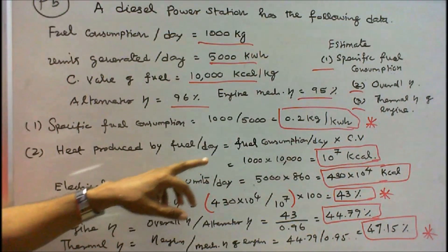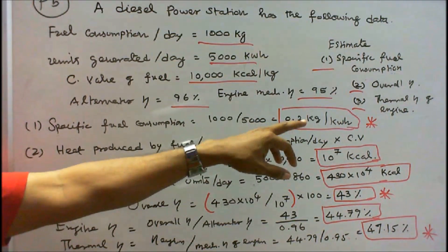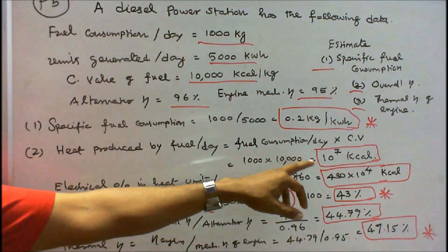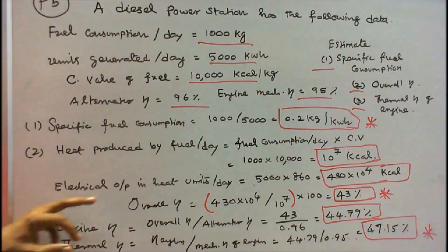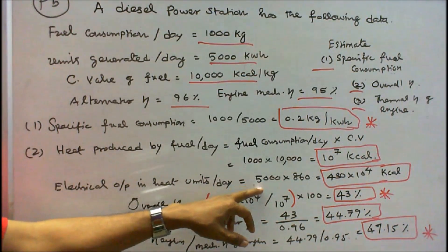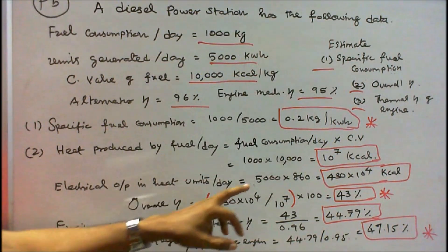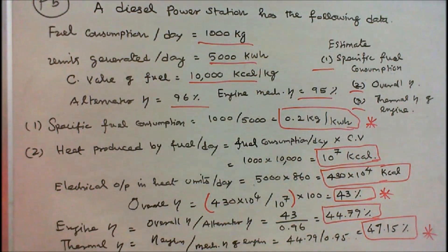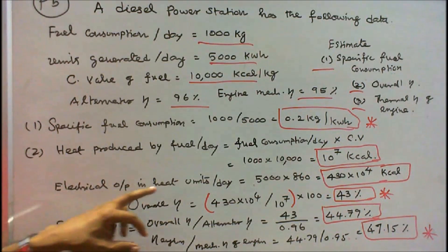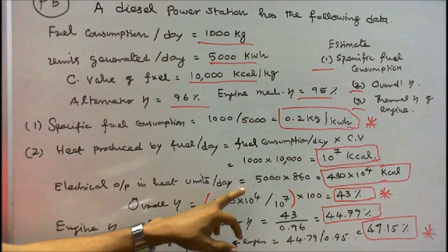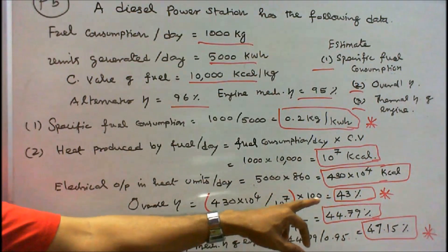Heat produced by fuel per day = fuel consumption × calorific value = 1000 × 10,000 = 10⁷ kilocalories. Electrical output in heat units per day = 5000 kilowatt-hours × 860 = 430 × 10⁴ kilocalories. Overall efficiency = electrical output in heat units per day ÷ heat produced by fuel per day = (430 × 10⁴) ÷ 10⁷ × 100 = 43%.